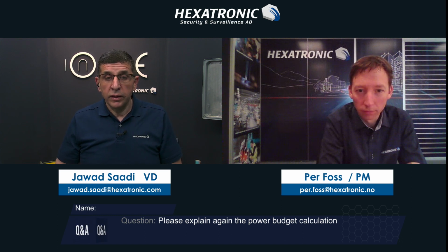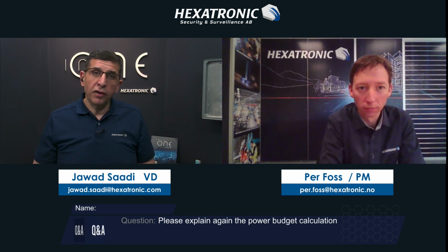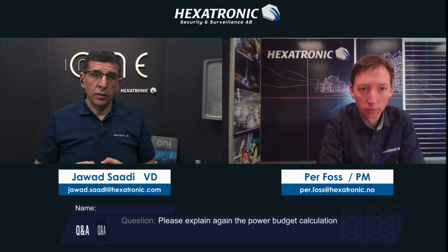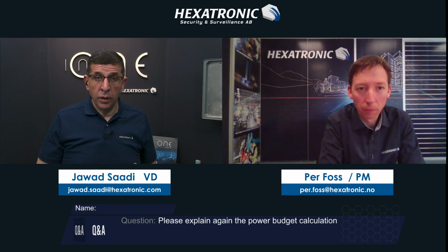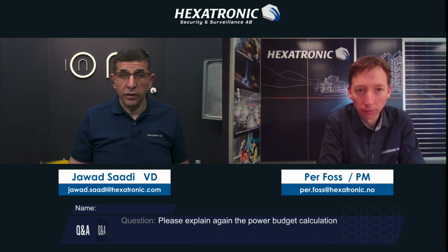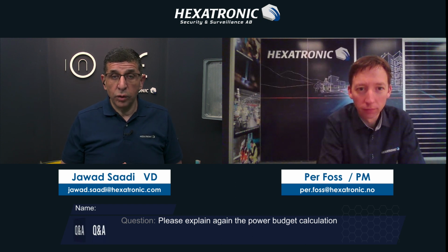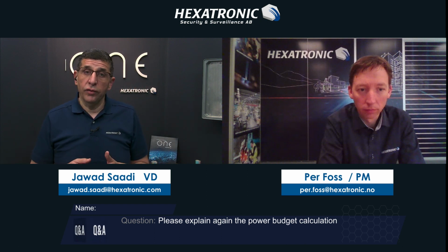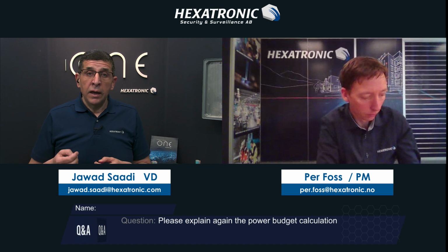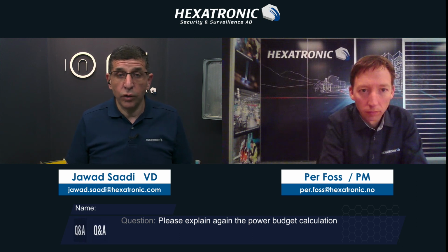Can you please explain the power budget? Okay, the concept of the power budget: from a fiber point of view, we have no worries. We'll never run out of fibers or distance with the InOne solution. We will have a limitation with the power before we have a limitation with the fiber. In the InOne, we start with 110 volts DC in the data center and 10 amps. Then when we have the wire running, you will have some losses due to the resistance in the cable. Now we have different diameters of cable. So if you have a bigger diameter, you have less resistance and you will have less voltage drop.